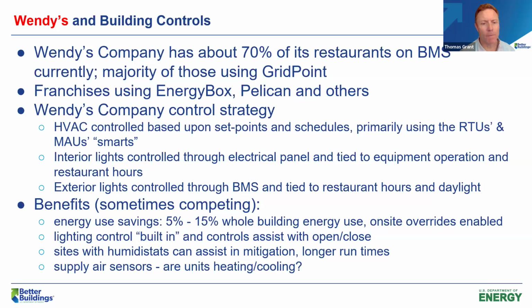Some benefits we've found: the 5 to 15% energy use savings figure is in addition to initiatives we'd already implemented, like LED lighting and efficient fan motors in walk-in coolers, freezers, and kitchen exhaust hoods—work my predecessors and Wendy's had already done. So the BMS savings shown here are on top of those other items, based on our whole energy use. We do have statistics on savings for certain pieces of equipment, but ultimately looking at whole building energy use is most important for us.